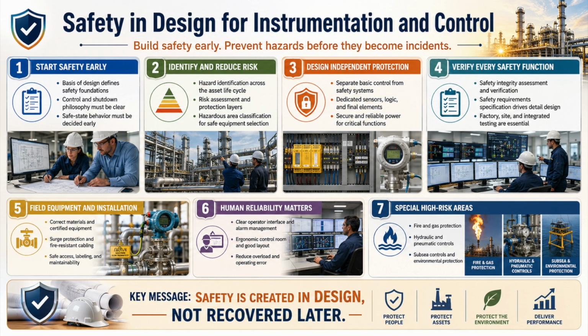Installation can preserve the design or destroy it. Instruments must be accessible from permanent platforms or ground level, wherever routine inspection, calibration, or testing is expected. Designers should not create maintenance activities that require temporary scaffolding, awkward lifting, unsafe body position, or unnecessary exposure to operating equipment. Field equipment must not obstruct walkways, handrails, escape routes, valves, or access to other equipment. Labels must remain readable during daylight, darkness, rain, and normal operating conditions.